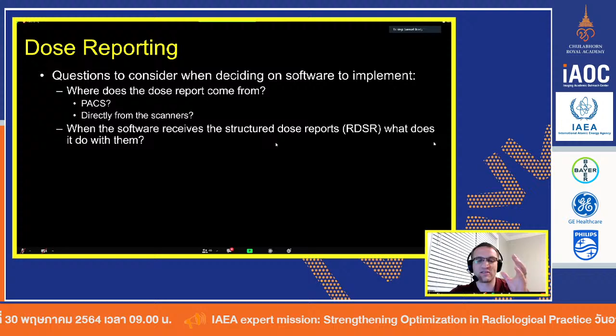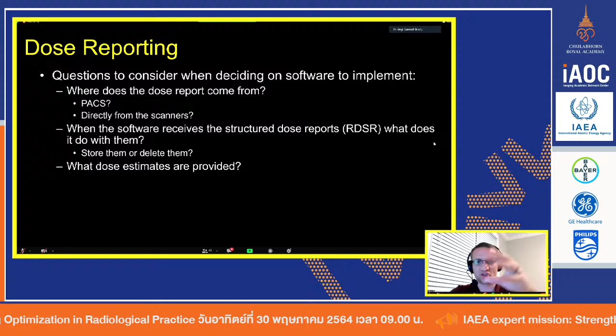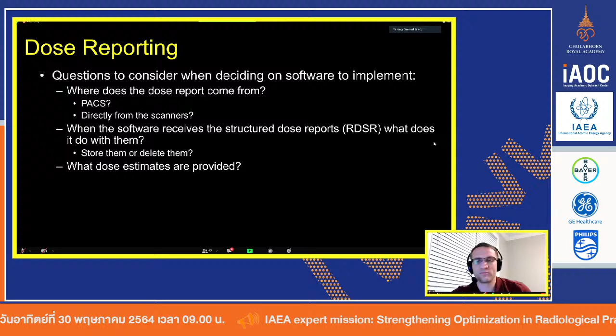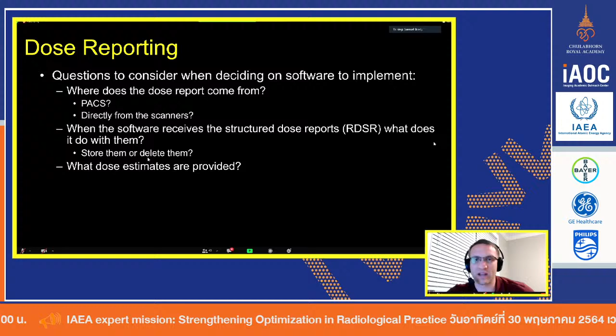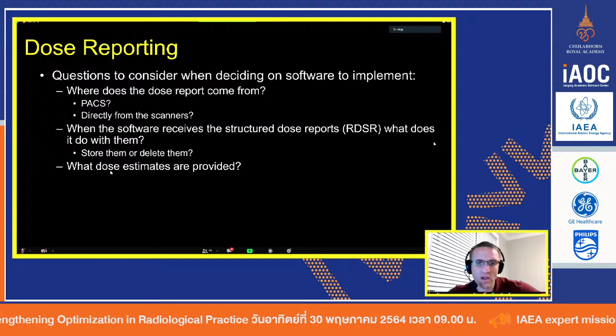And so you have to know which one the system receives, or can it receive both of them? And then after it receives it, does it collect it forever? Does it keep it in its server? Or does it scrape the data off, store it in its software, and then delete the structured dose report? Which is fine, but I've found that if they're not deleting them, the process gets bogged down, and eventually your server starts going slower and slower and slower as you put more and more data into it.